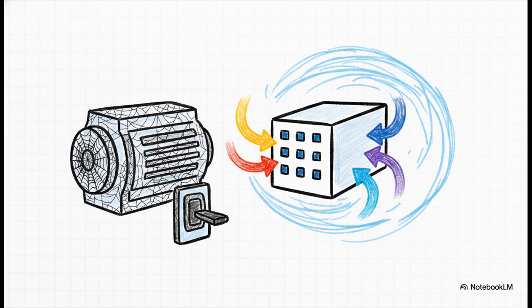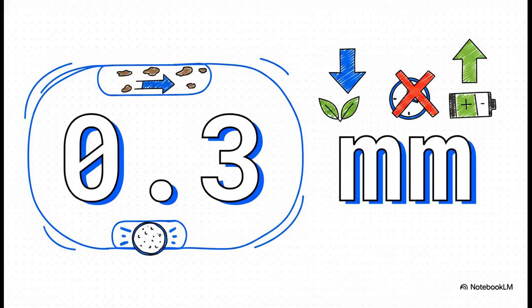This is called total free cooling. It allows them to literally shut off their giant power-hungry compressors all winter long. The energy savings are just insane. Now, think about the number 0.3 millimeters. Super thin, right? Well, if just 0.3 millimeters of scale, basically hard water stains, builds up inside a condenser tube, the cooling efficiency tanks by a massive 10 to 15%. No way you pass ISO 50001 with that kind of waste.